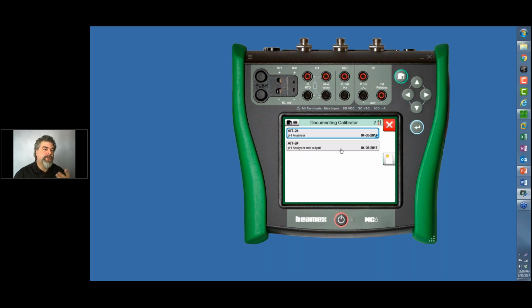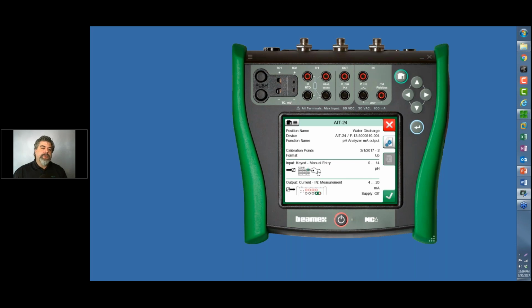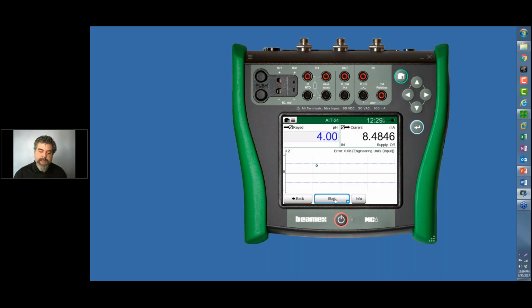We're not doing that. We have a transmitter that's doing part of this work for us. So with the transmitter, we will input what pH we're showing, and then we'll measure the current. So this one, the range of pH is 0 to 14. And the range of current is 4 to 20. I'm not providing loop power because this thing is already being powered. So let me start this up. And let me hit start. And you're going for a ride again. Hold on.